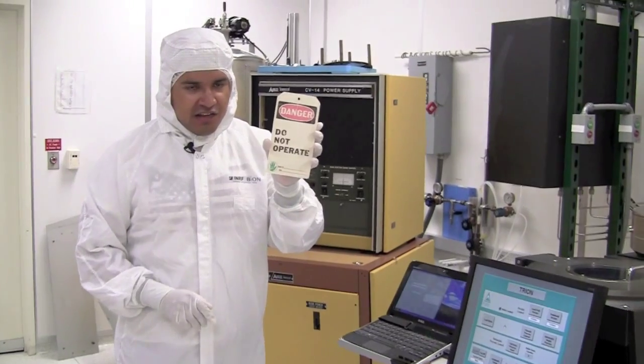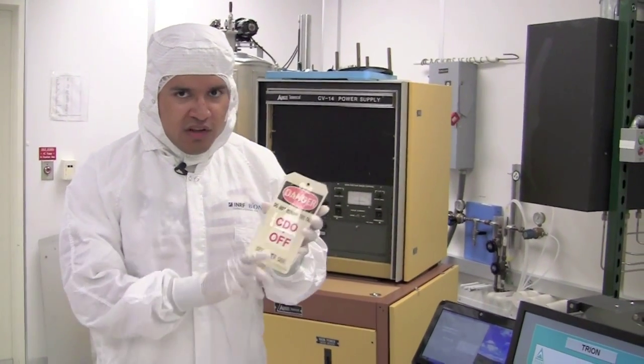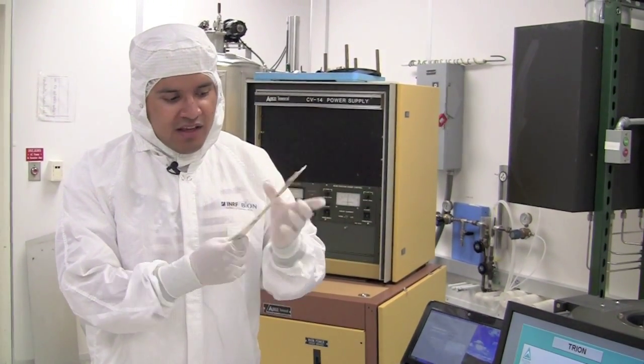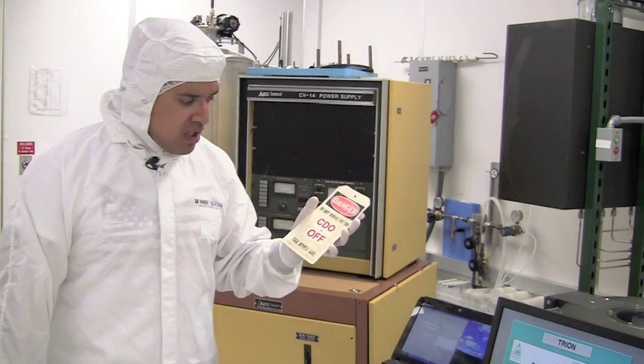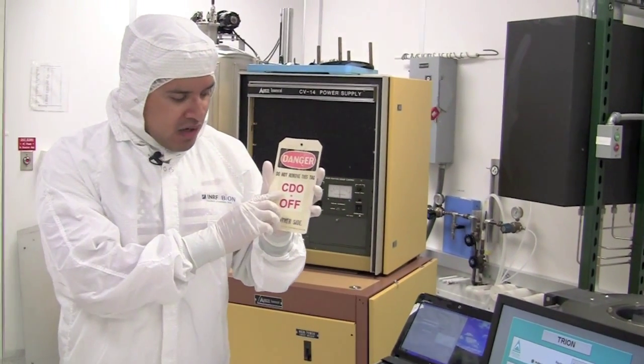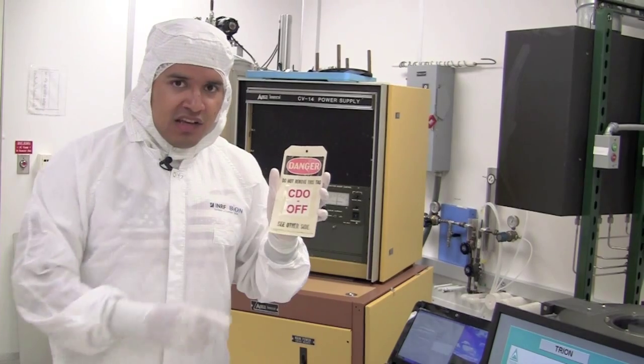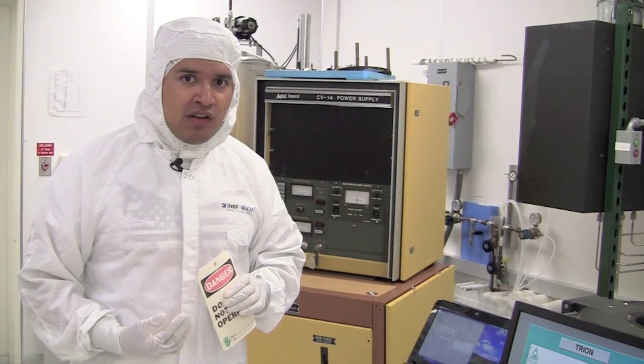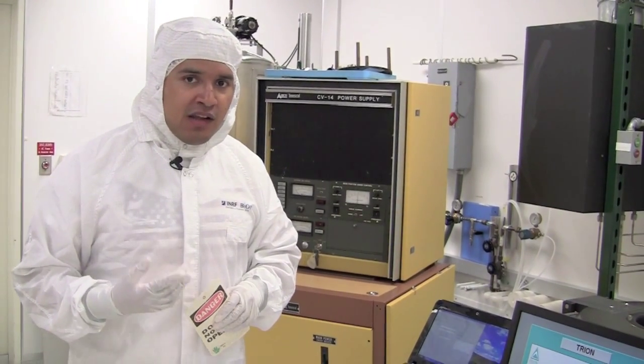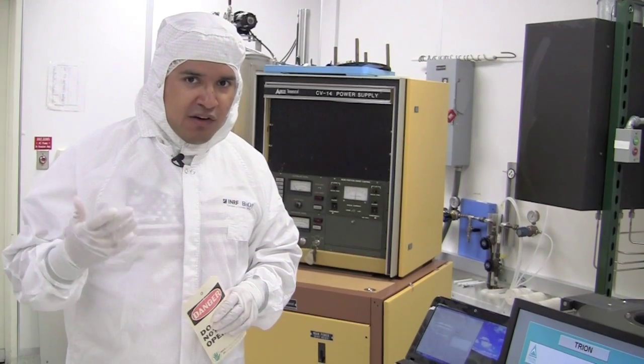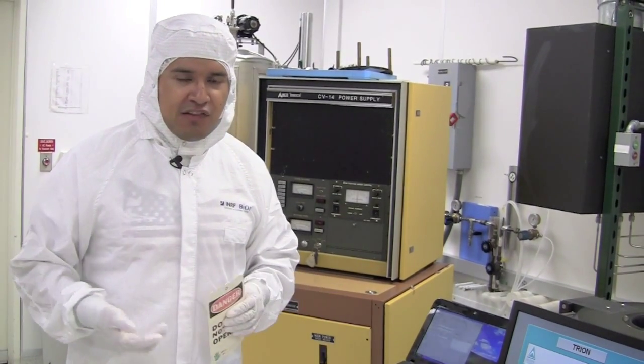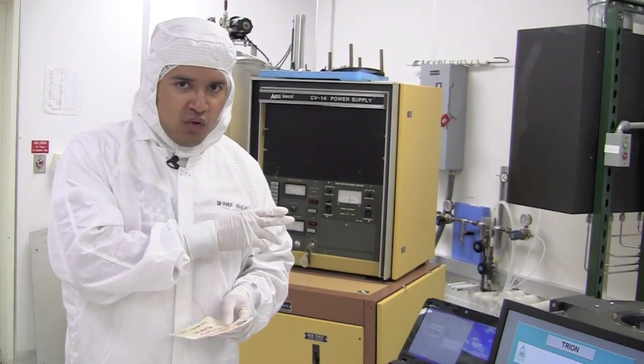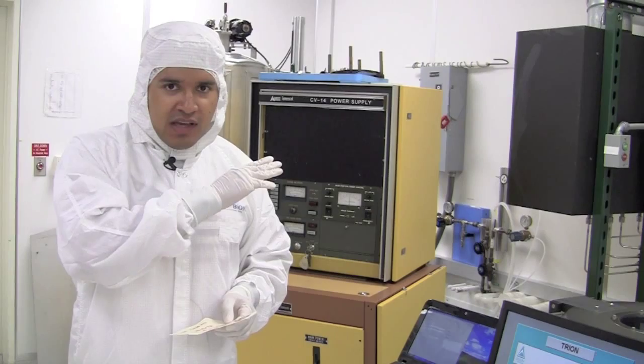First you'll see this sign. This sign, whenever you see it, whether it's on this side or this side, means the tool should not be operated before checking some things in the chase. So a do not operate is a little more vague, a CDO is a more specific message. You may be wondering, what's a CDO? Well, CDO or controlled decomposition and oxidation is just a burn box that takes leftover chemicals that are not used during a reaction and burns with oxygen in a high temperature. Then this is released to the atmosphere so that whenever we have chemicals that need to be expelled into the atmosphere, they'll be more inert and less reactive. It's better for the environment and for safety. So it's important to make sure that tool is running in the background before we start using this tool because we don't want to pump any gases through and directly into the atmosphere.